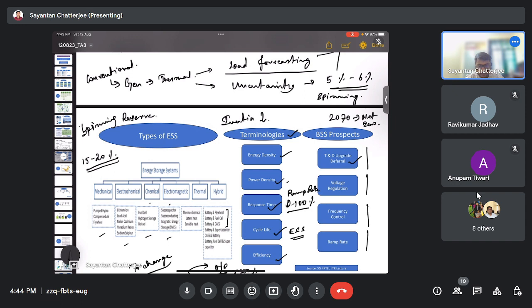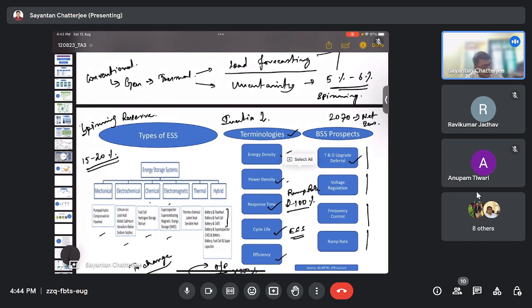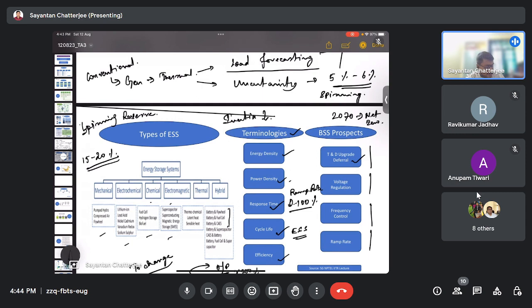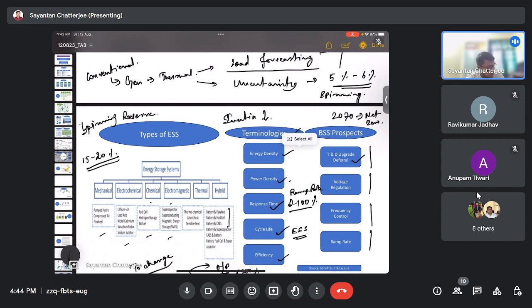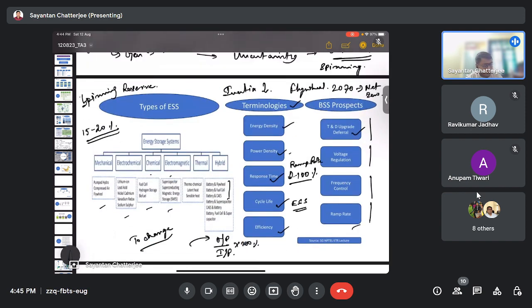So the grid inertia is gradually decreasing, and with that decrease the problem is the uncertain behavior of the renewables. Due to this uncertain behavior, it cannot meet the sudden variations, and for that we need to commit more and more generators, more thermal or rotating masses in the system, and sometimes flywheel mechanisms also play a part. So this is the main scenario, and these are the main advantages of using battery energy storage systems.